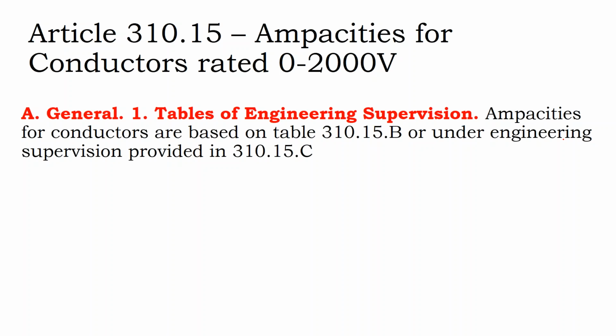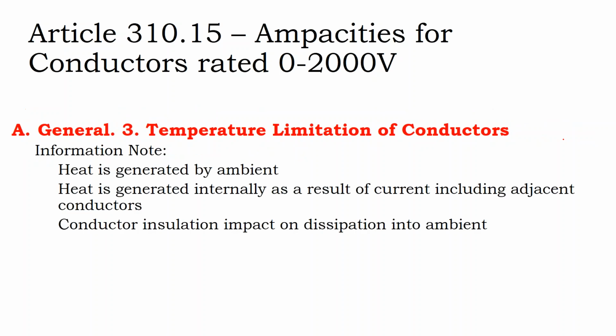And I think that's a little bit more dangerous because the building codes are not as well organized as the electric code. But what we have in the NEC are tables that are basically fudge factors that allow an electrician to spec out wire sizing in a safe manner that mirrors closely the results of your engineering data. But you're allowed to not use the tables and instead calculate your wire sizings off of engineered calculations when you're using a professional engineer to perform those calculations and stamp them.